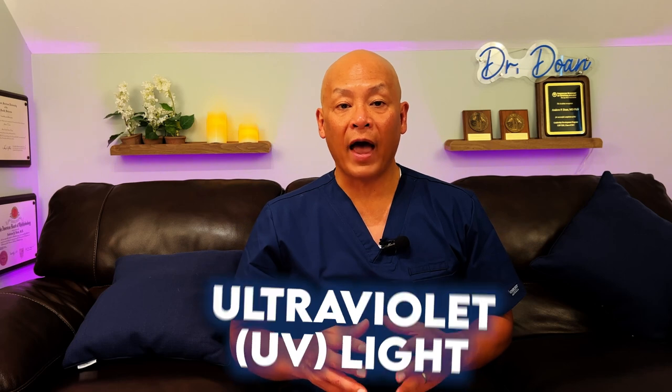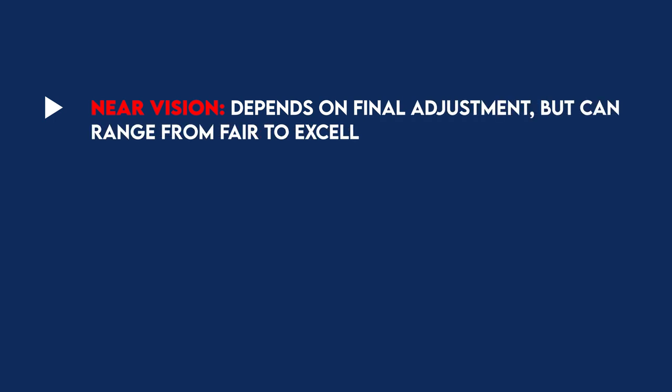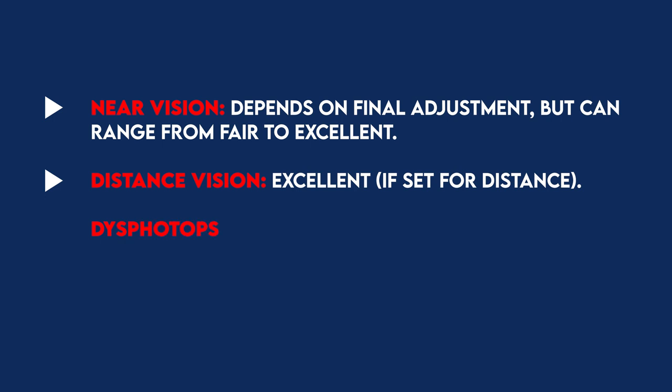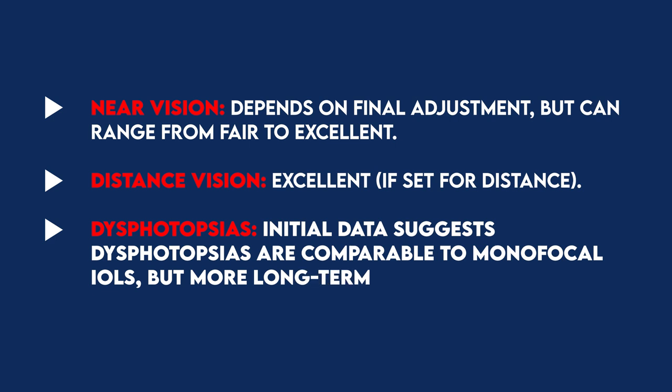The light adjustable lens is made of a special photosensitive material that changes the shape and power of your implanted lens. UV light is used after surgery to optimize your vision. The light delivery device non-invasively delivers UV light to precisely reshape your lens based on the visual correction needed to target your custom prescription. Near vision: depends on the final adjustment but can range from fair to excellent. Distance vision: excellent if set for distance. Dysphotopsias: initial data suggests rates are comparable to monofocal IOLs.